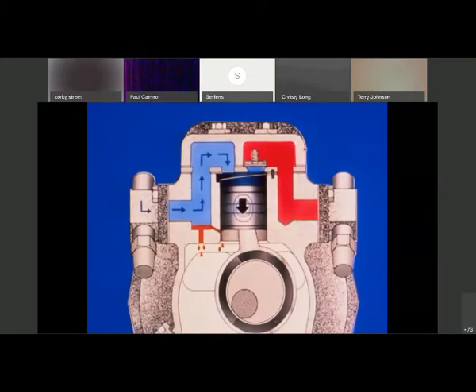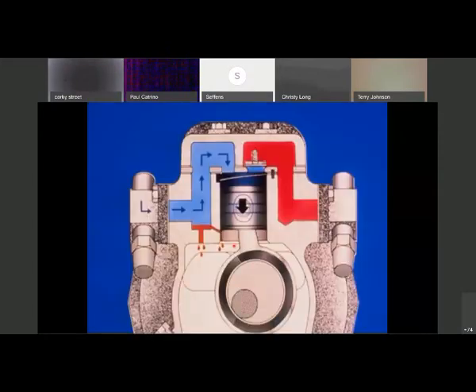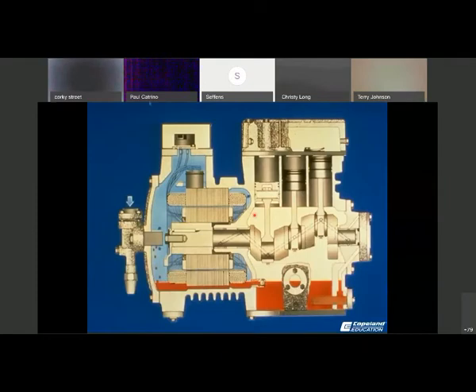One thing I didn't talk about yesterday - refrigerant-cooled compressors: we have two types. We have air-cooled compressors and refrigerant-cooled compressors. Air-cooled compressors have to have a minimum of 650 FPM across the body of the compressor to keep it cool while it's running. Most of these compressors are located in condensing units where fans are used not only for condensing purposes but also to help cool the compressor itself.